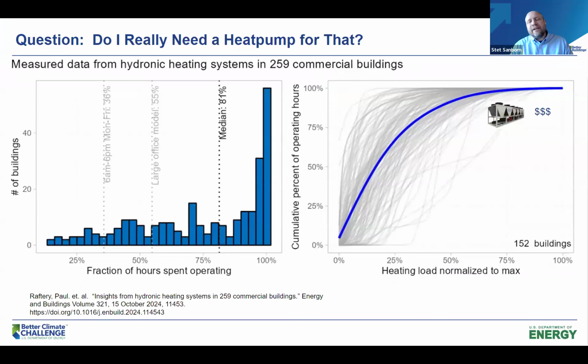Something else I want to share is some recent research that's going to be published next month, and we are lucky to get a sneak peek of it. Researchers at the Center for the Built Environment at UC Berkeley went in and measured heating loads across the U.S. in 259 commercial buildings. This curve on the right is the one that's really compelling. I know you're like, great, another graph, but this is a really compelling graph, and you should be excited about it. It essentially shows that for 75% of the hours the heating system is running, it is running at 30% capacity. 90% of the year, you're at 50% capacity.